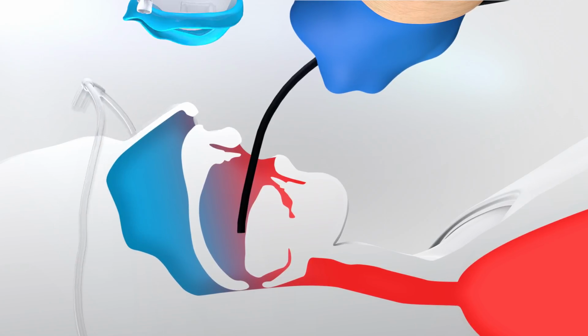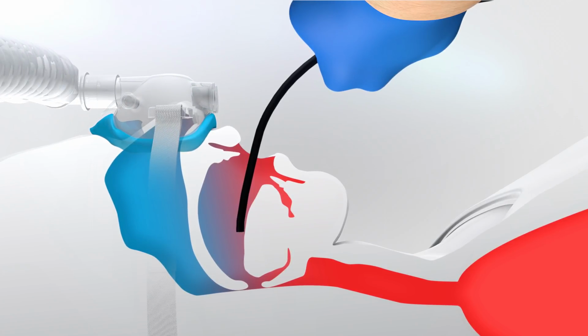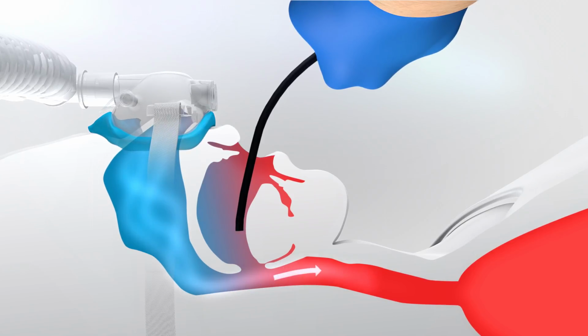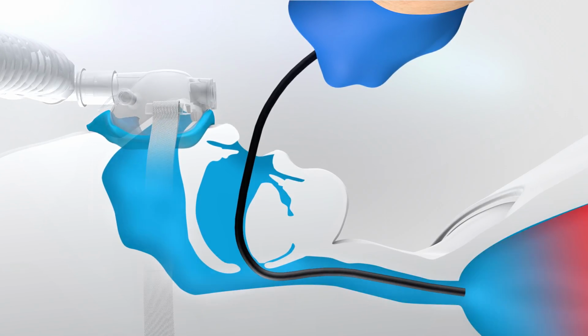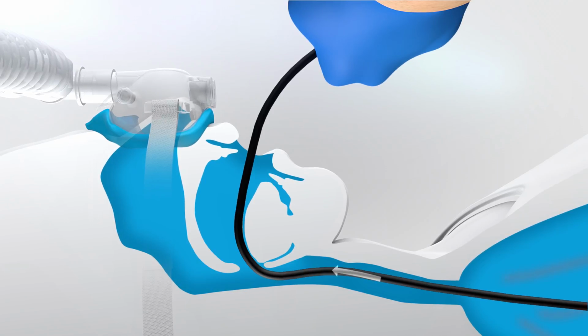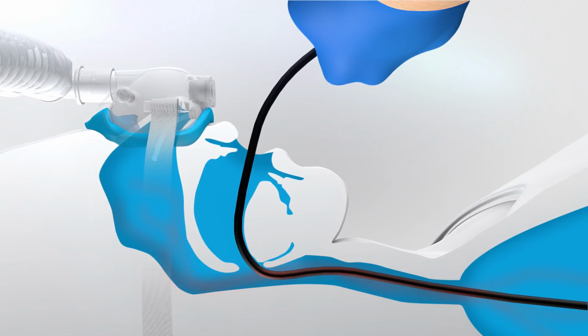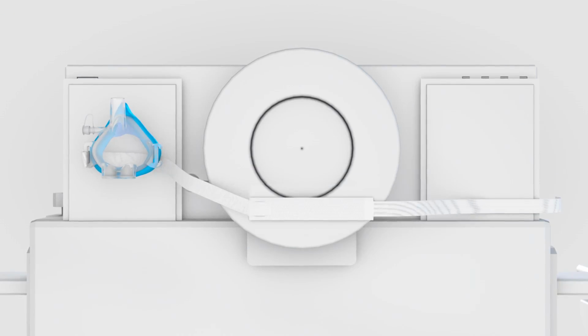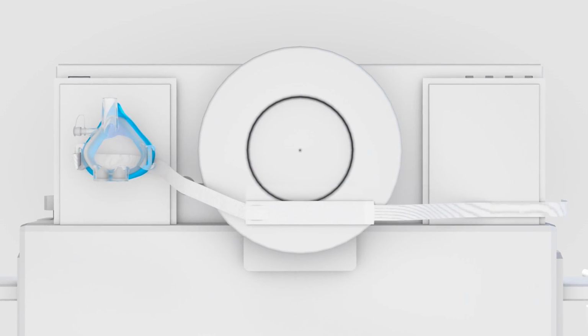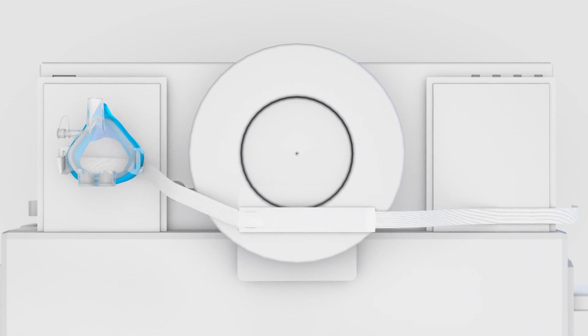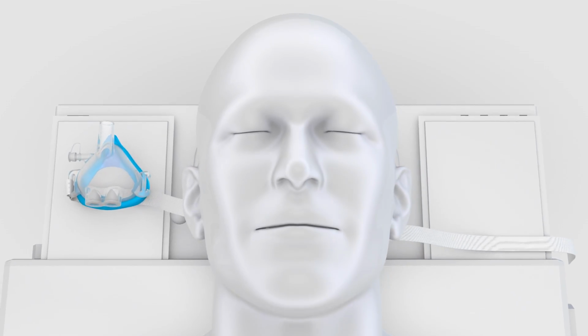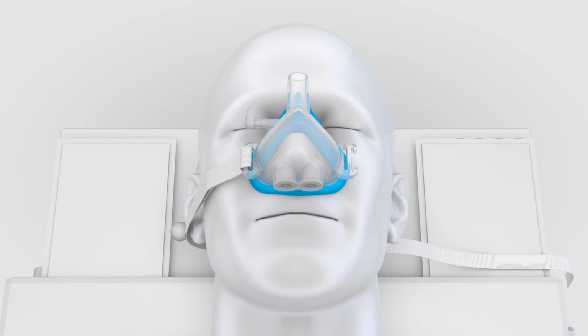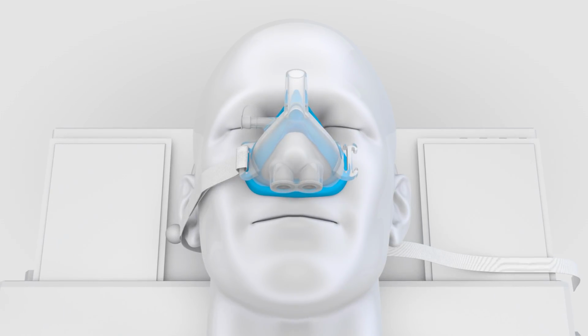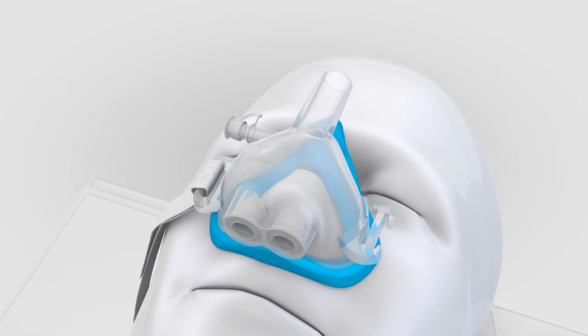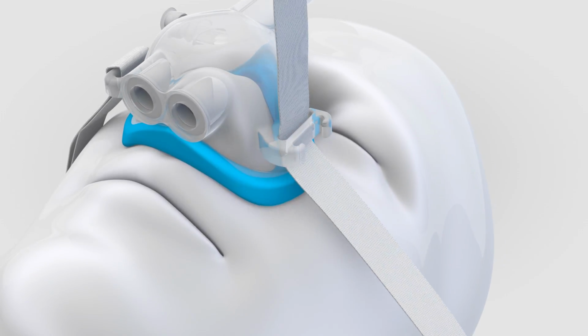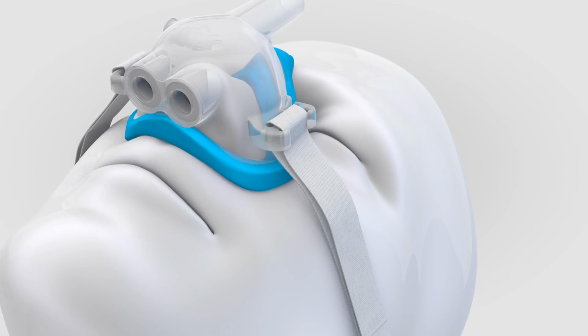The SuperNOVA device's ergonomic TPE seal makes contact with the skin and is designed to prevent air leak among a large demographic population. It remains low profile on the face, allowing for direct physical and visual access to the oral cavity. Lay the head strap on the procedure table where the head will be placed, with the SuperNOVA device to the patient's right. With the head resting over the strap, place the mask over the patient's nose with circuit connection pointing cephalad. After wrapping the SuperNOVA device head strap around the head, loop it into the cleat and secure it to itself using the hook and loop contact points.